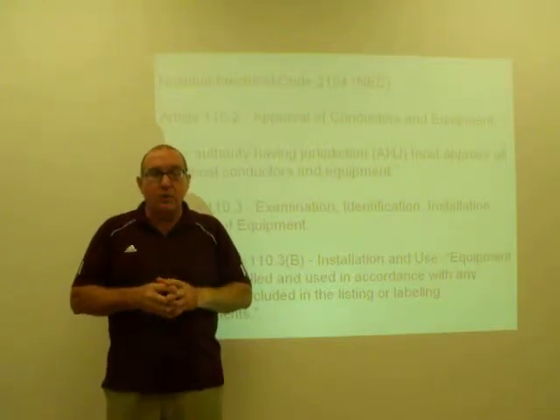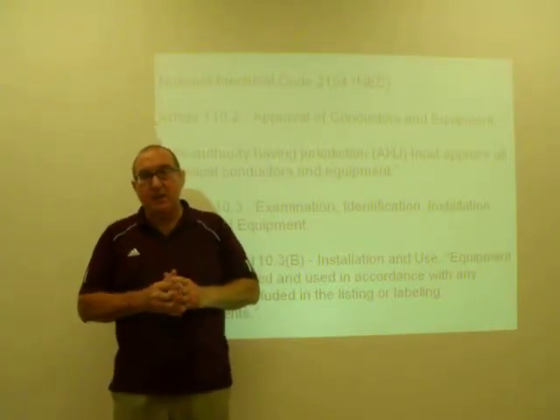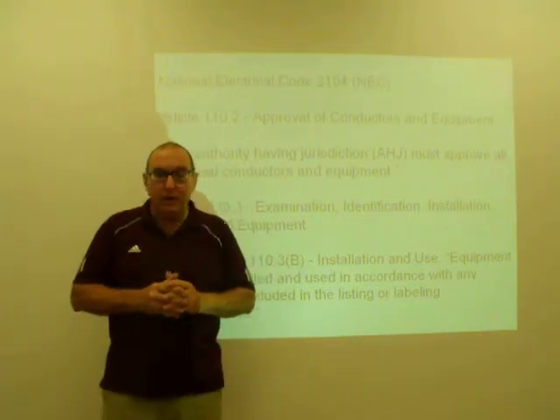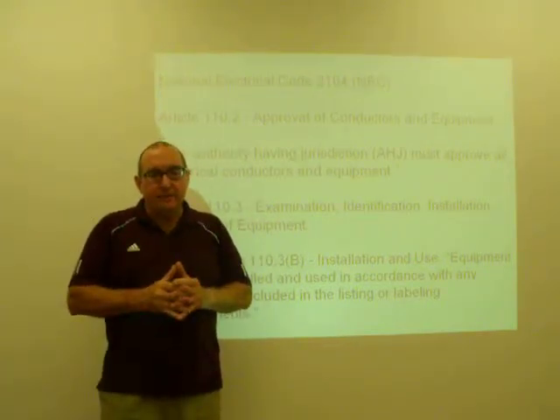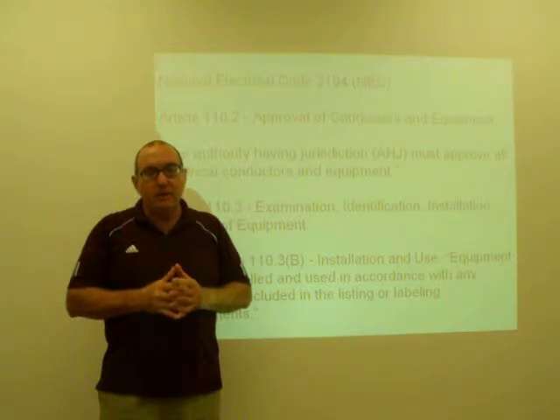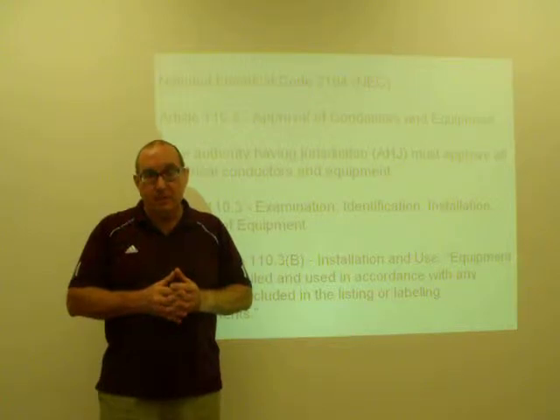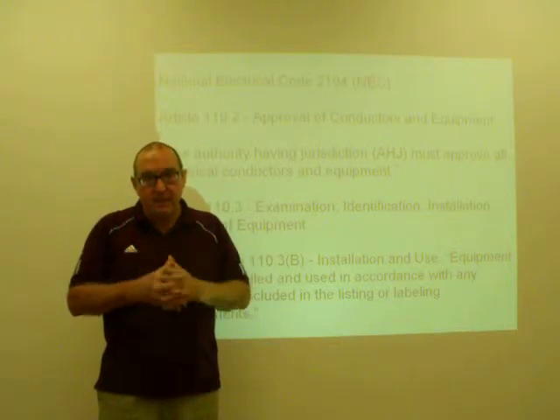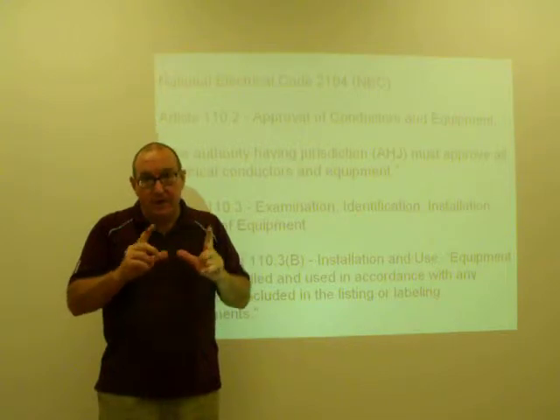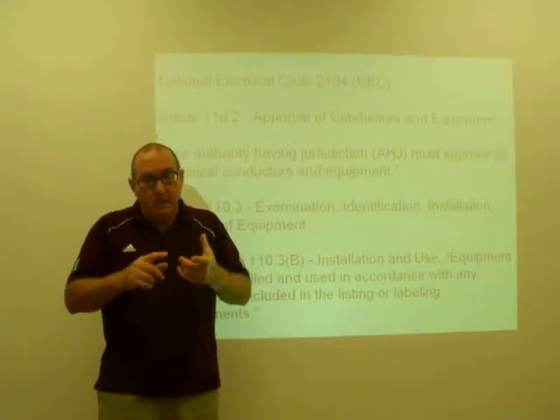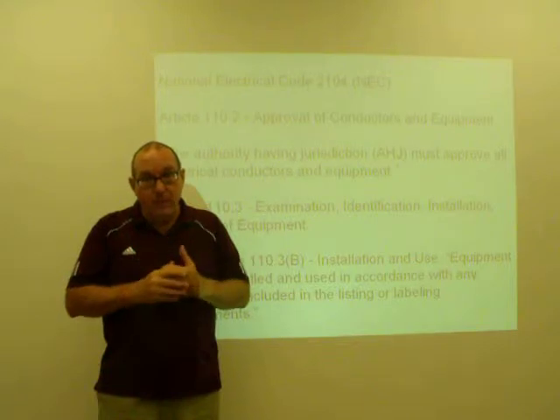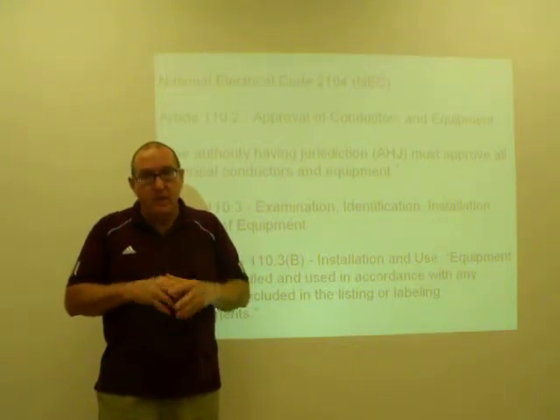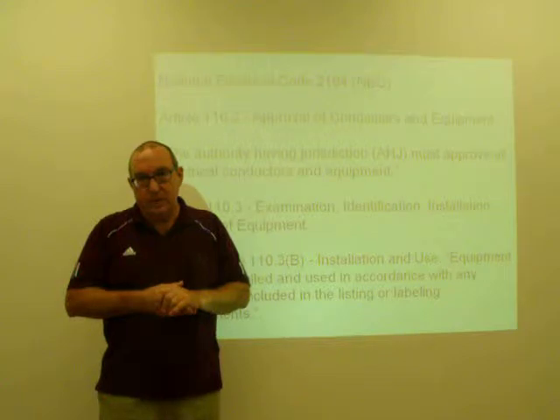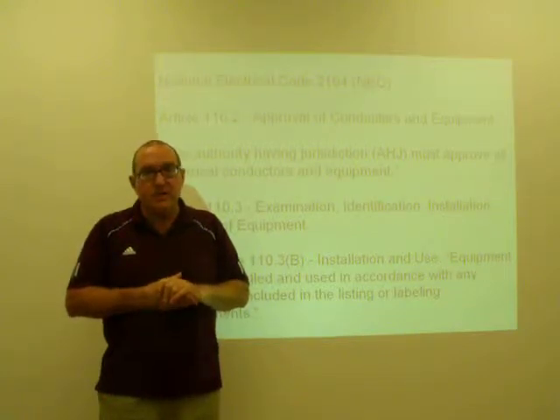The second one is Article 110.3, specifically subparagraph B in that article, which states that equipment must be installed and used in accordance with any instructions included in the listing or labeling requirements. So inside the cover of every panel board, there is typically a paragraph or two, some sort of description that says what you can do, what you cannot do with that panel board in terms of the types of breakers you can install, the quantities of breakers you can install, and so forth. And so the code requires that you must comply with those listing and labeling instructions.